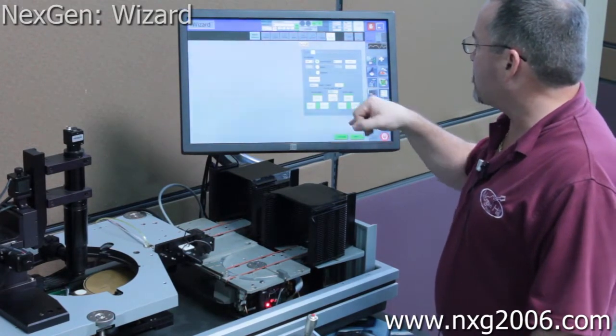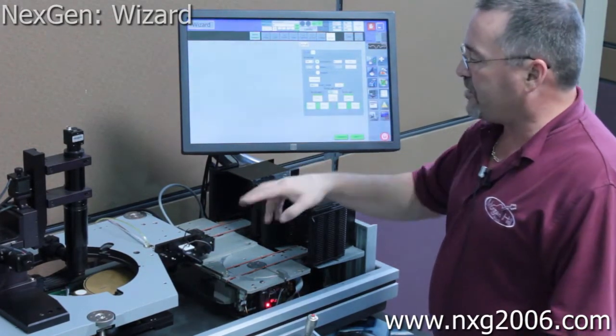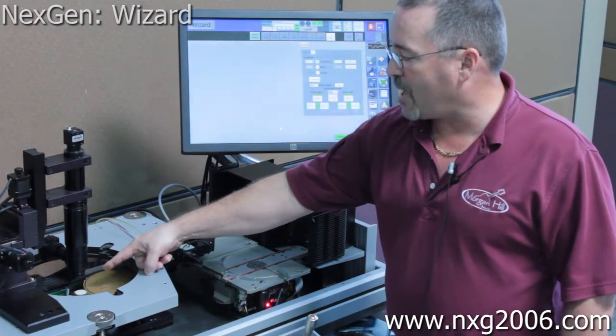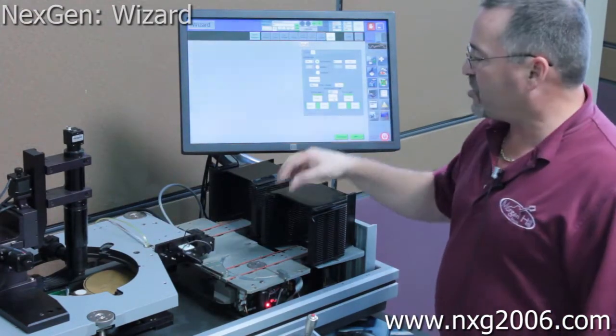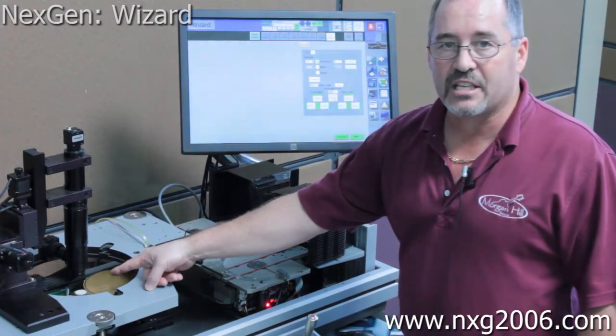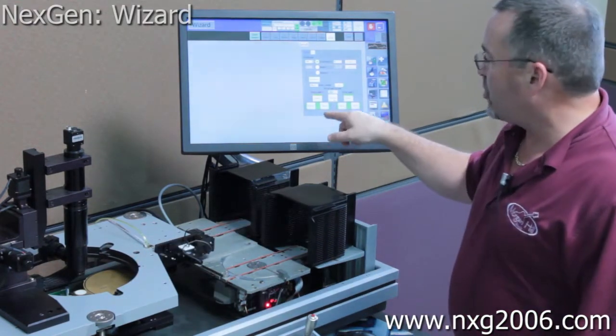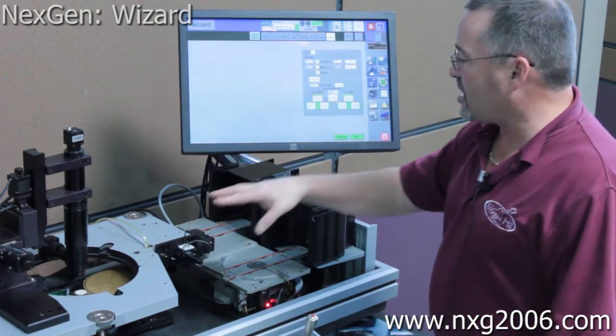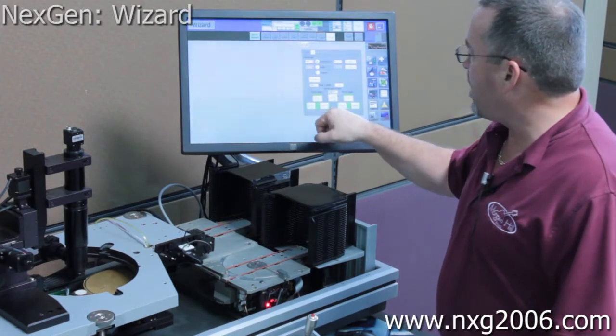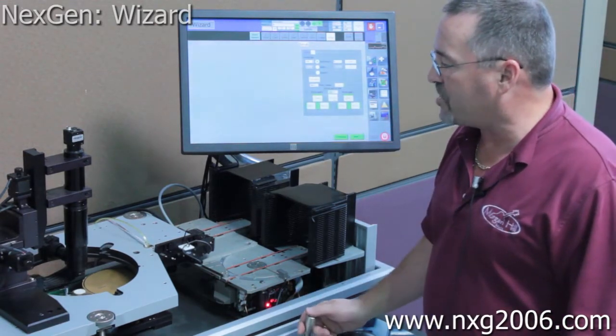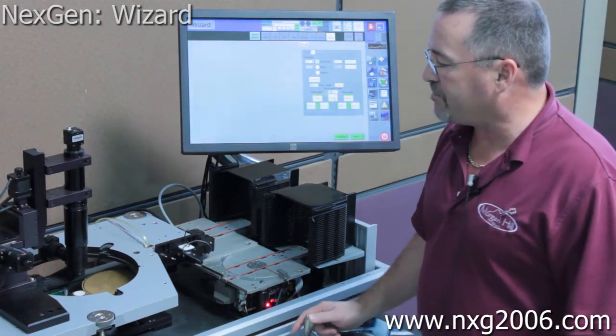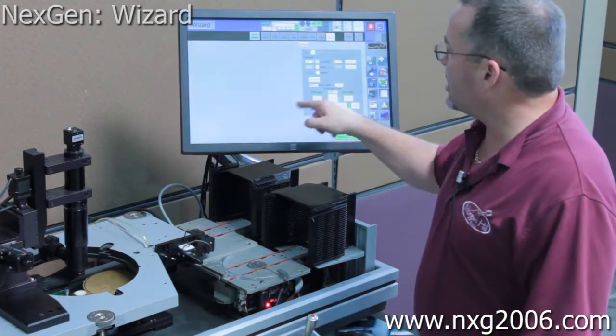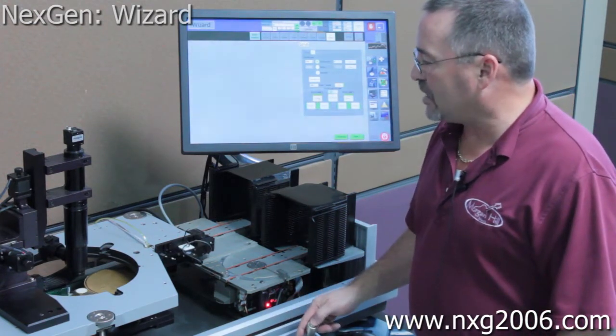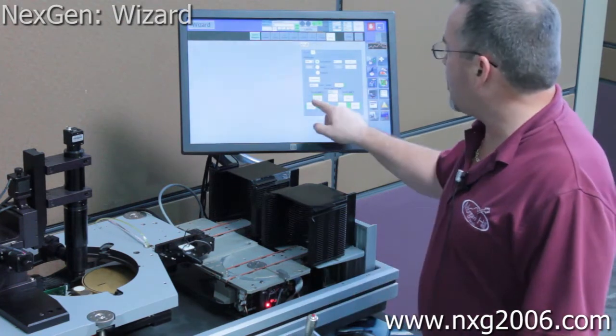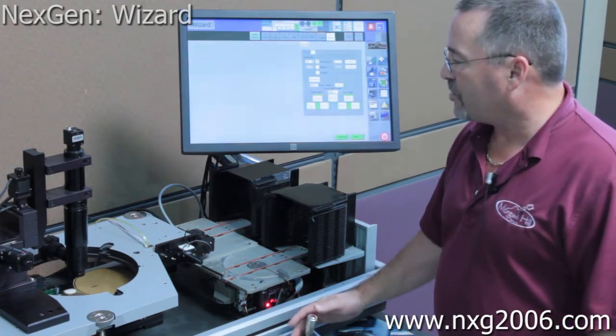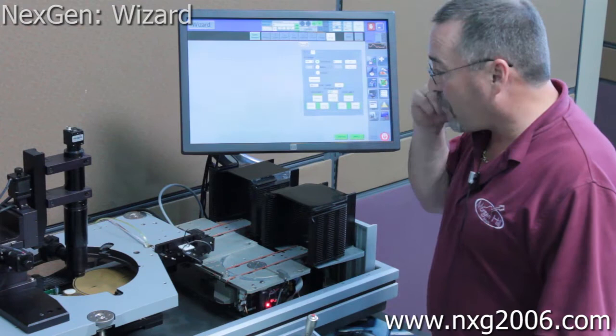We have scrub pad 1 and scrub pad 2. Scrub pad 1 on this check would be the ceramic one on the top towards the back of the machine. Scrub pad 2 would be the tungsten version that's towards the front of the machine. So what you have to do is, if it's not in the area, you need to set up the new parameter of where that's going to be. So if I wanted to move this around a little bit to a spot, I want to say there's my starting spot. Then I got to move to the left a little bit, creating like a little bit of a triangle. Set point 2, set point 3.